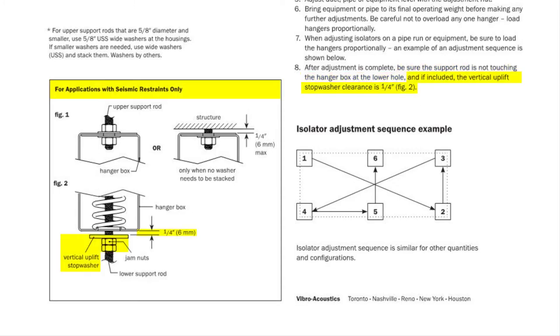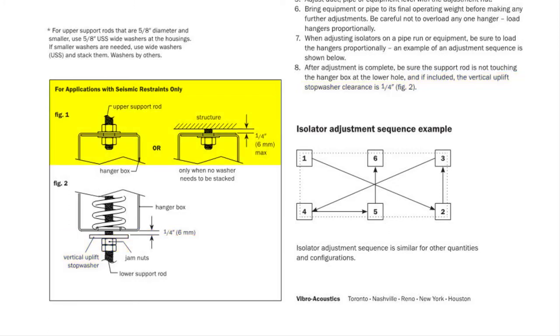On installations where the spring hanger box is near a seismic cable restraint, it is important to add a vertical uplift stop washer and to make sure it is a quarter inch away from the bottom of the hanger box. It is also important to secure the top of the box with either an upper support nut or by mounting the box tight to or within a quarter inch of the supporting structure. Both of these are to prevent excessive vertical movement during a seismic event.